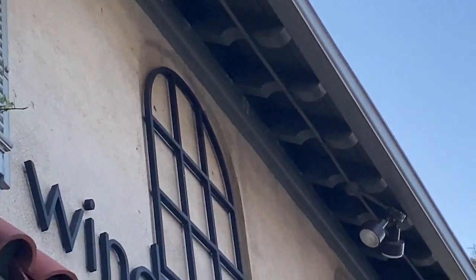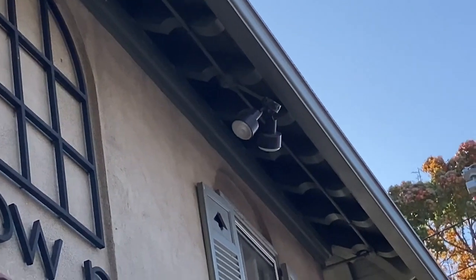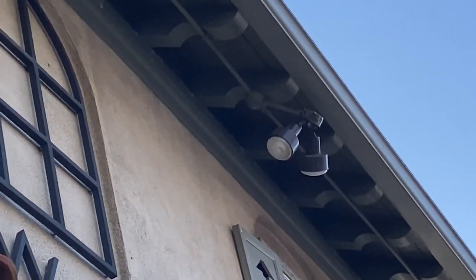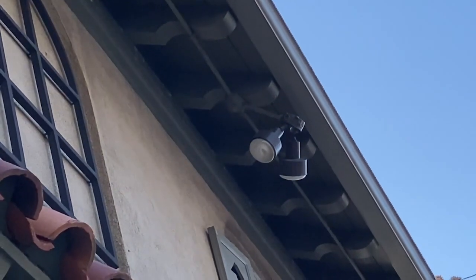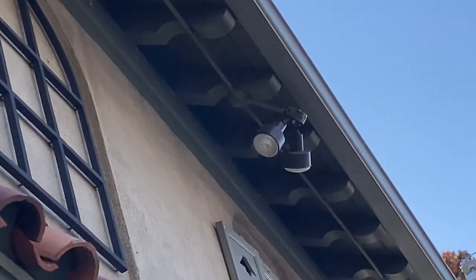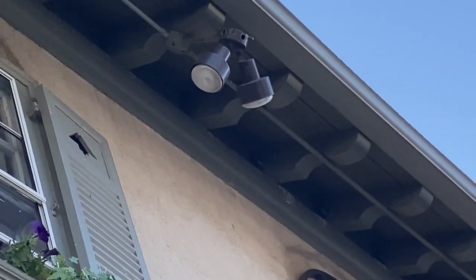Look up there. There's another one over here, and those light fixtures are just kind of dangling out there on the end of that raceway. The installer attached the box with the light fixtures onto a raceway that's threaded into another box which is secured. So essentially this one raceway is securing the box with the light fixtures.